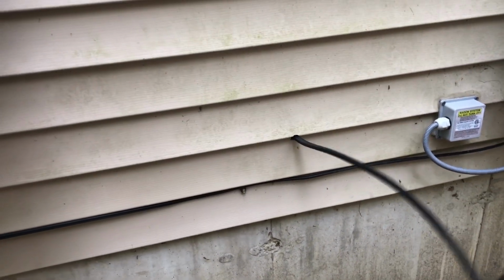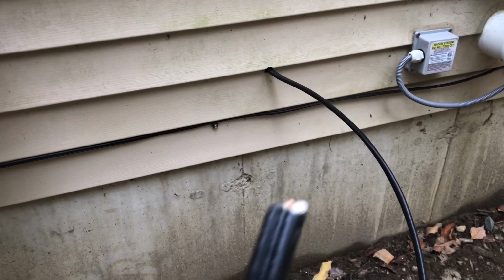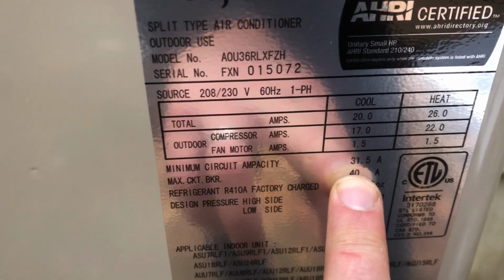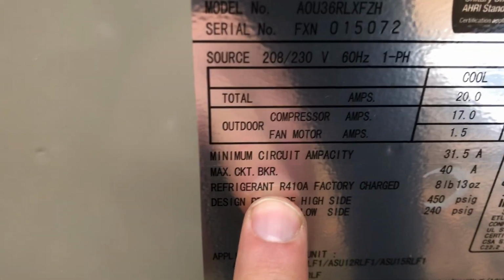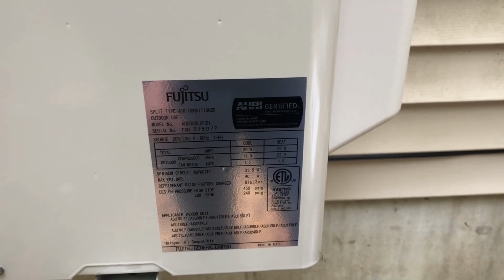So this wire, this is the one end that I've got that's going to go into my disconnect box. But before we get to that, I want to talk about the appropriate size wire. If you look at the panel on this air conditioner or any air conditioner, it's going to tell you the amperage. It says the minimum circuit ampacity is 31.5. And then it tells me the maximum circuit breaker, 40 amp. So that tells me that I needed a 40 amp circuit breaker inside the house. You need to get the appropriate one for your box. So if you have a GE box, you're going to get a GE breaker. You need a double pole breaker because this requires 220.